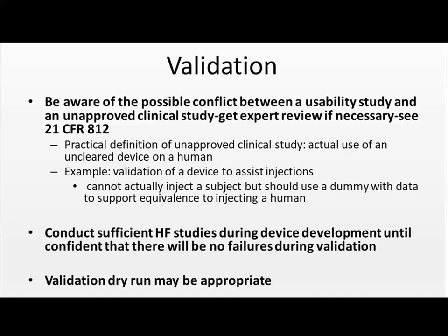Another point, you should conduct sufficient human factor studies during device development, called the formative studies, until you're confident that there'll be no failures during validation. You want the validation to be no surprises. You want the validation to be the documentation of a successful development. So you should conduct sufficient preliminary studies beforehand.